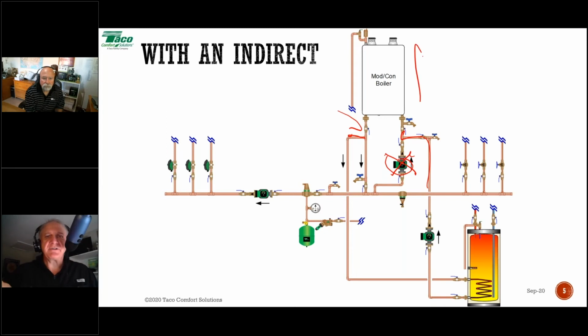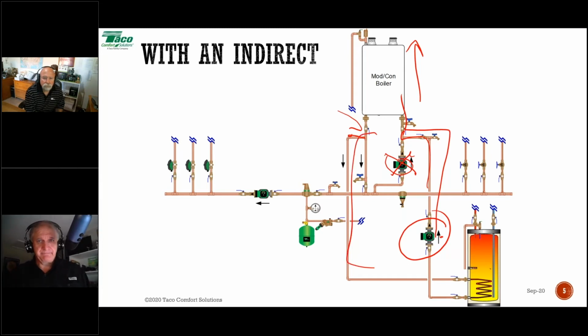The boiler fires up to, traditionally, different boilers might do this differently, but it'll fire up to whatever its highest temperature is, typically 190. And then this circulator for my indirect is initiated. Again, it's pumping into the high head loss heat exchanger, and our flow obviously goes through the heat exchanger of the indirect, and it bypasses the delivery.